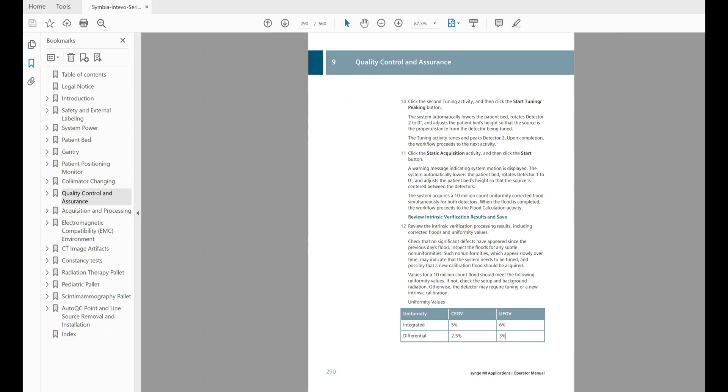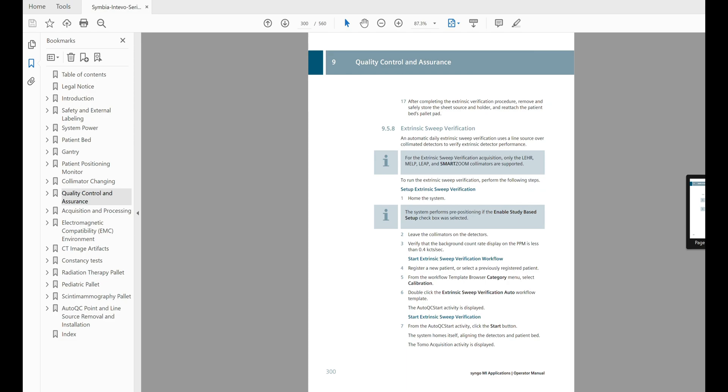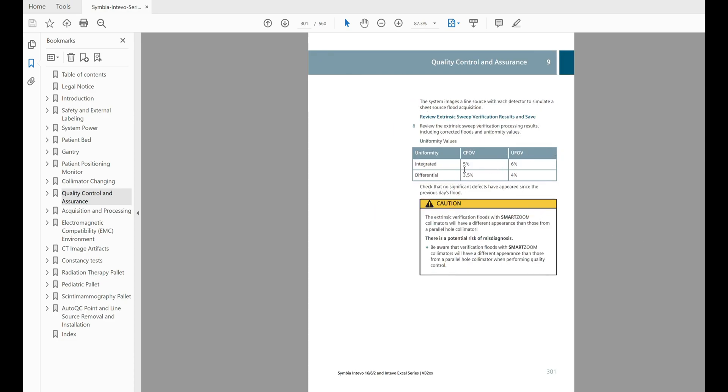For the differential UFOV it's three percent, and for the differential CFOV it's two and a half percent. Now these are all intrinsic values for 10 million counts — these values will be different for extrinsic. Flipping over to page 301, we see the extrinsic values. We still have six percent and five percent for the integral UFOV and CFOV; however, for the differential we're now at four percent and three and a half percent — slightly higher on the extrinsic differential.